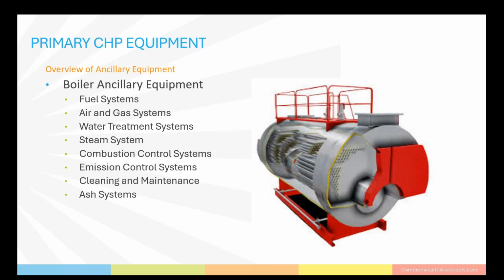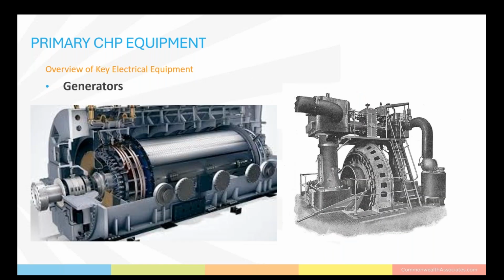Boiler ancillary equipment depends on the fuel, and that could be tanks, additional tanks, pumps, filters, heaters for the fuel, air compressors and filters, gas meters and regulators, water softeners, filters and pumps, burner management system, flame detectors. You may need selective catalytic reduction. If you're burning biofuels, you'll need electrostatic precipitators, soot blowers, water wash systems, boiler cleaning equipment. And then in addition, boilers utilizing biofuels are going to need ash conveyors, ash storage silos, and ash handling systems.